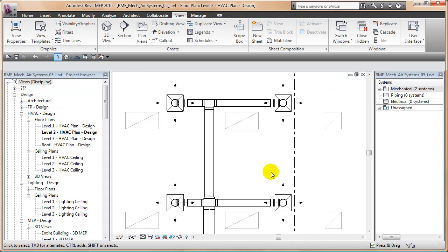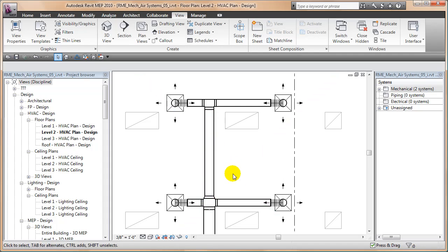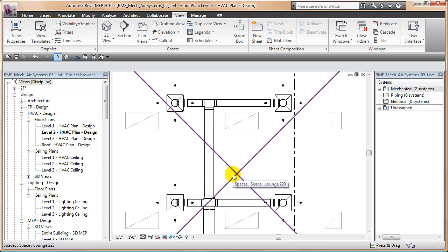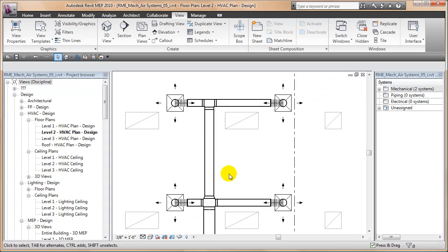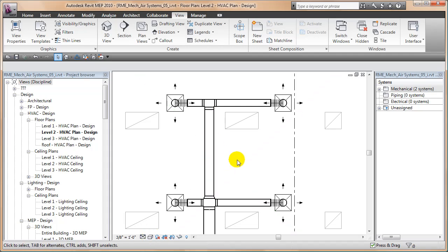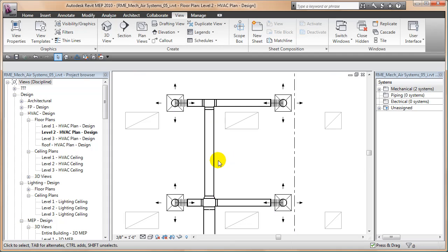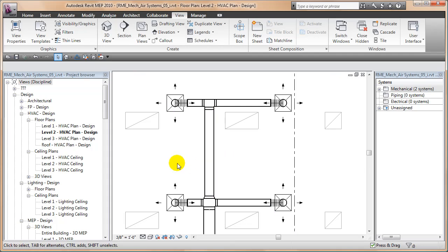So the challenge here is to be able to see center lines on our ducts or pipework in Revit MEP in hidden line view. And the answer is to use a filter to filter out the round ductwork and then use visibility graphics to make them transparent. So this is what we do in this particular challenge.